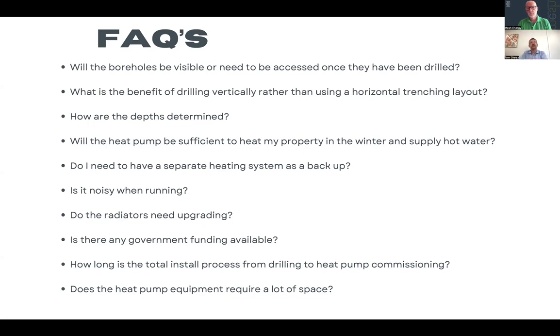But that depends. My advice to clients is, if there is an option to do any upgrades in the construction of the building, provide cavity insulation, loft insulation, I would always suggest doing this first, because that will reduce the size of the heat pump system required. That will reduce the running cost of the system, and also the cost of the system. If you upgrade the cavity insulation and loft insulation and reduce the total heat demand by a significant number, you're then reducing the number of boreholes required, the size of the heat pump, and your ongoing running cost.